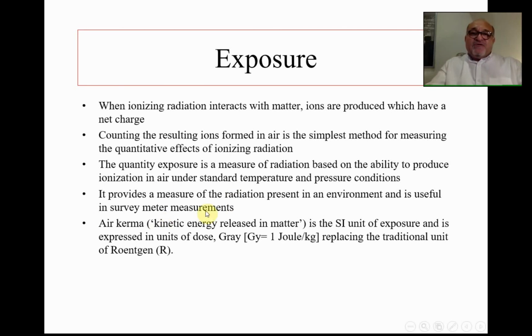The quantity exposure is a measure of radiation based on the ability to produce ionization in air under standard temperature and pressure conditions. It provides a measure of the radiation present in an environment, not in a tissue, and is useful in survey measurements. So actually what we have here is X-ray, ionizing radiation or gamma ray, and then we will have ionization of air. There is no tissue, no biological tissue, no biological effect here. It's the measurement of ionization of air. Thus it measures quantity, not the quality, not the energy given.